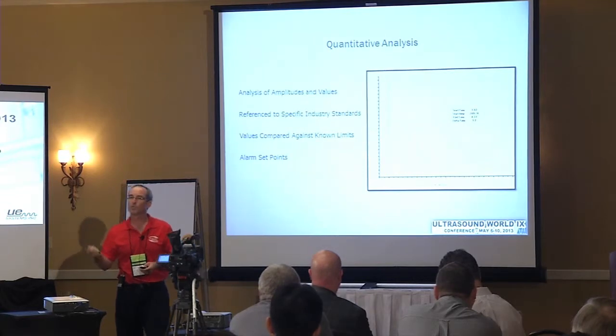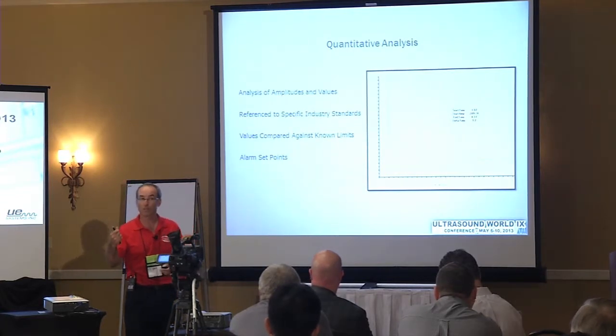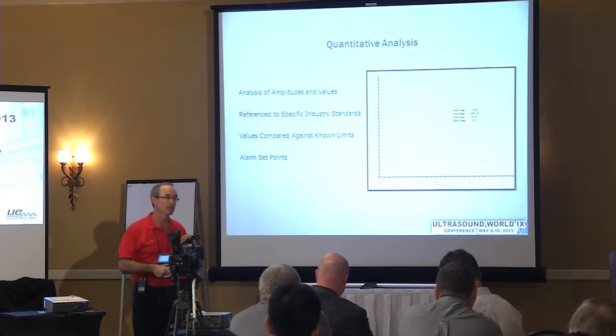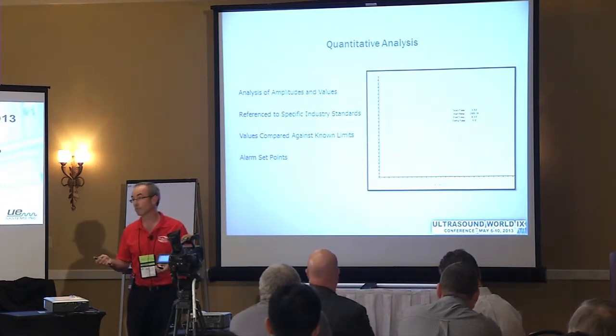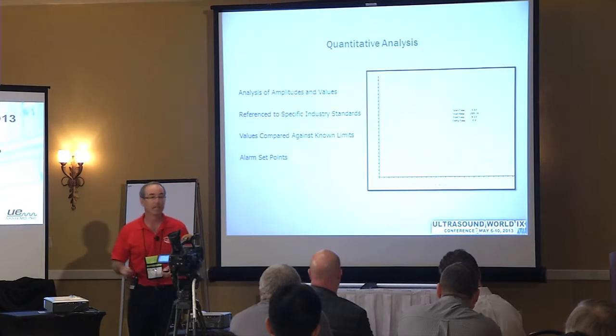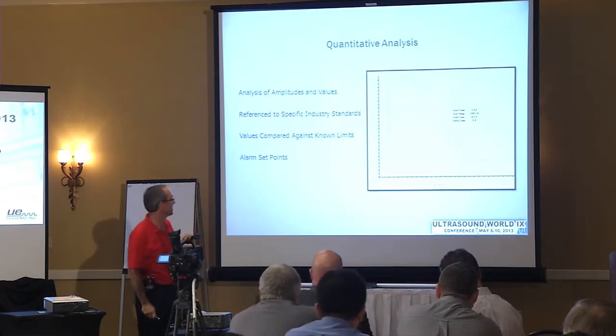Now some of the motors are changing these days, so if you're able to get a current reading on some of these motors, recognize that some are being designed to exceed 10 times their full load amps for inrush. It shouldn't surprise you, but here's the thing — it won't surprise you if you get that baseline, right? That's such a good baseline to have. So yeah, you should definitely be getting that.